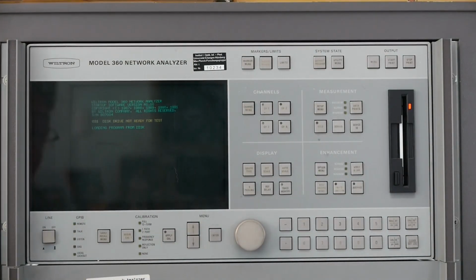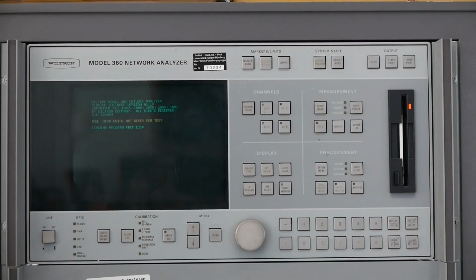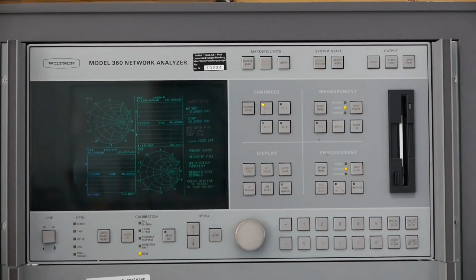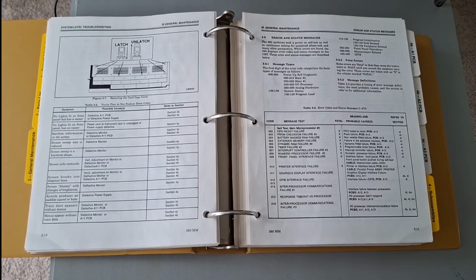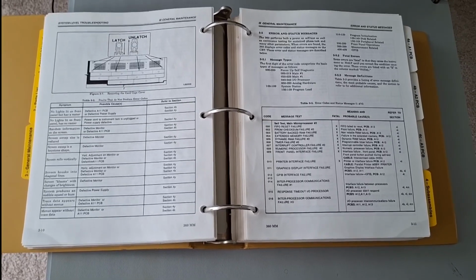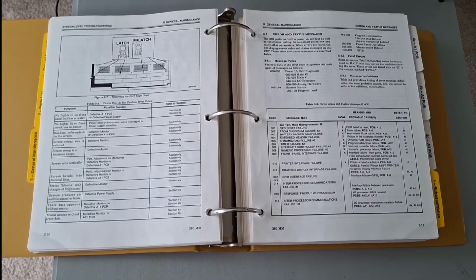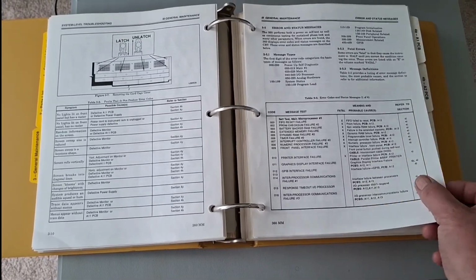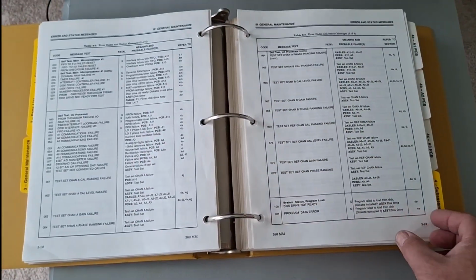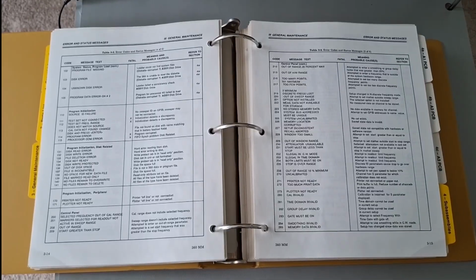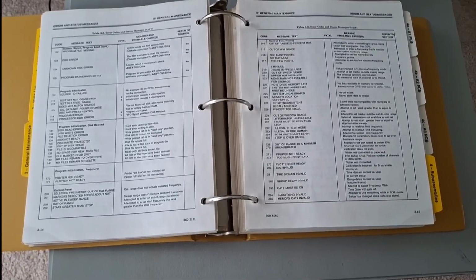Loading program from disk, so that's working. Takes a lot longer than I remember to load a program from a 3.5-inch floppy drive. Okay. You're looking at the service manual for the VNA, and it has chapters on fault finding. And in these chapters there are error codes. There are pages and pages of error codes indicating what the built-in test equipment is finding.